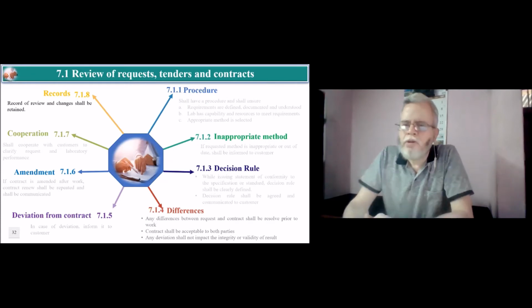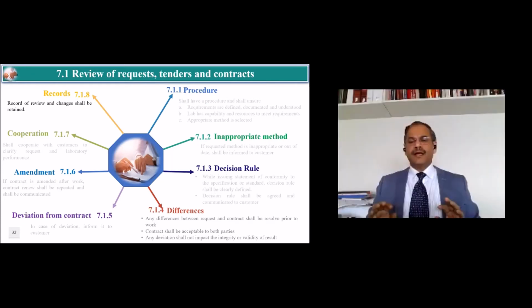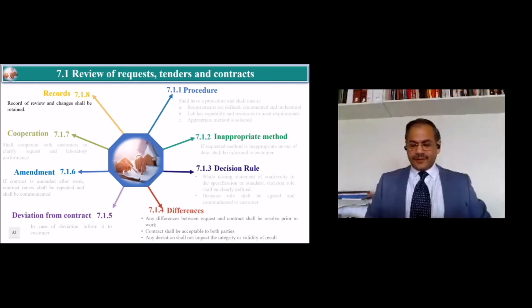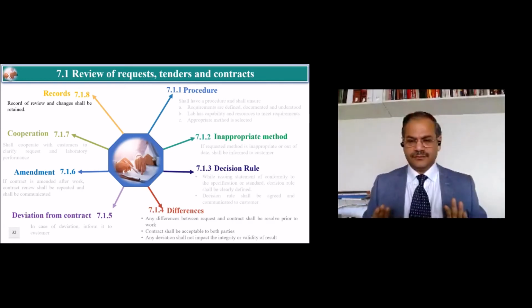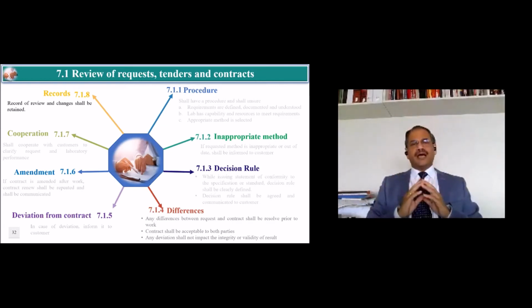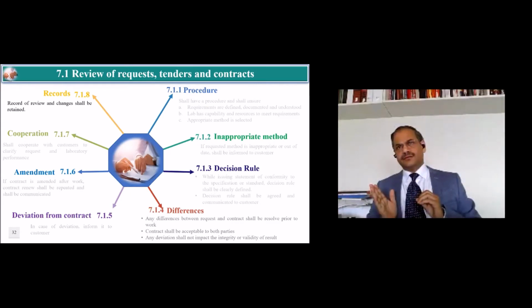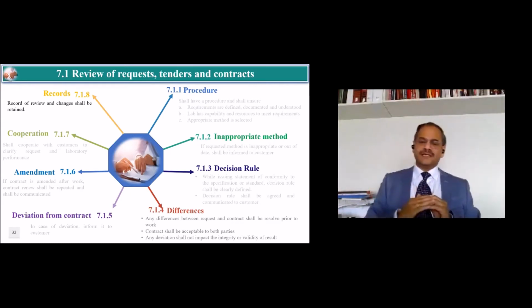Yeah, sure. Sir, one question came: should we have SOPs for each equipment and test method? What do you think? Again, you have to go to the standard. If you compare with the old standard, we are still in the mental setup of the old standard, which said you shall have. Here, you have to perform the risk assessment. Do you think if I do not have this document, my people are going to deviate from the testing? If the answer is yes, you shall have. If the answer is no, you need not have.